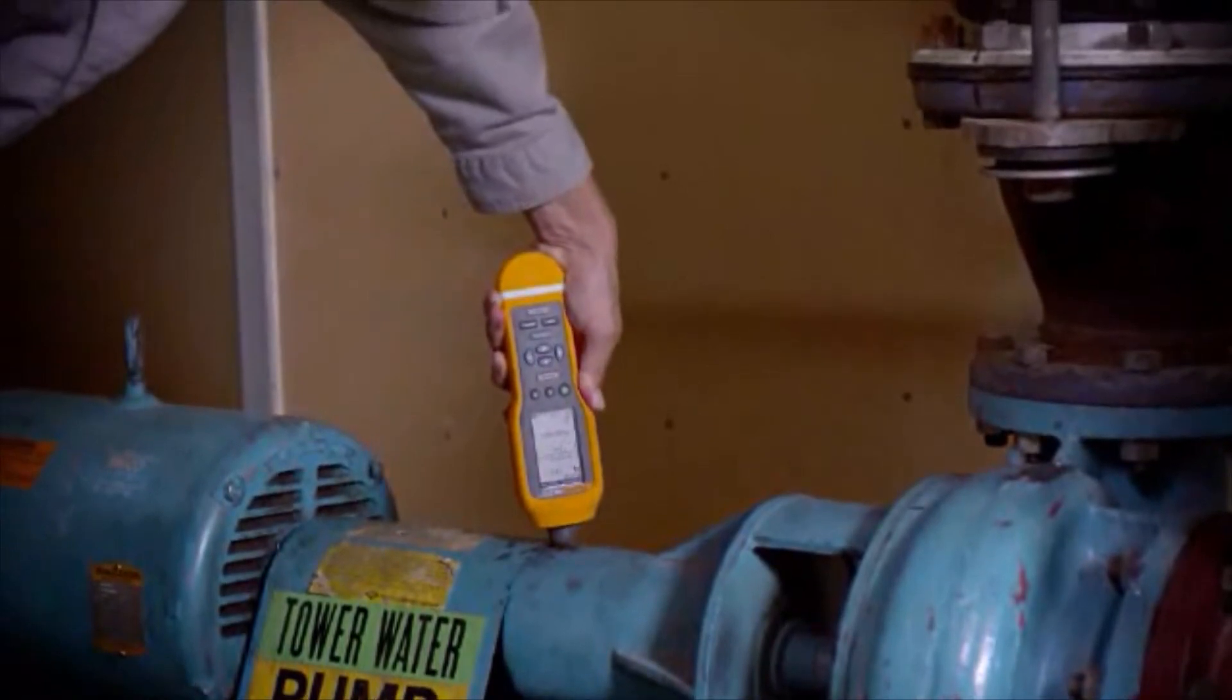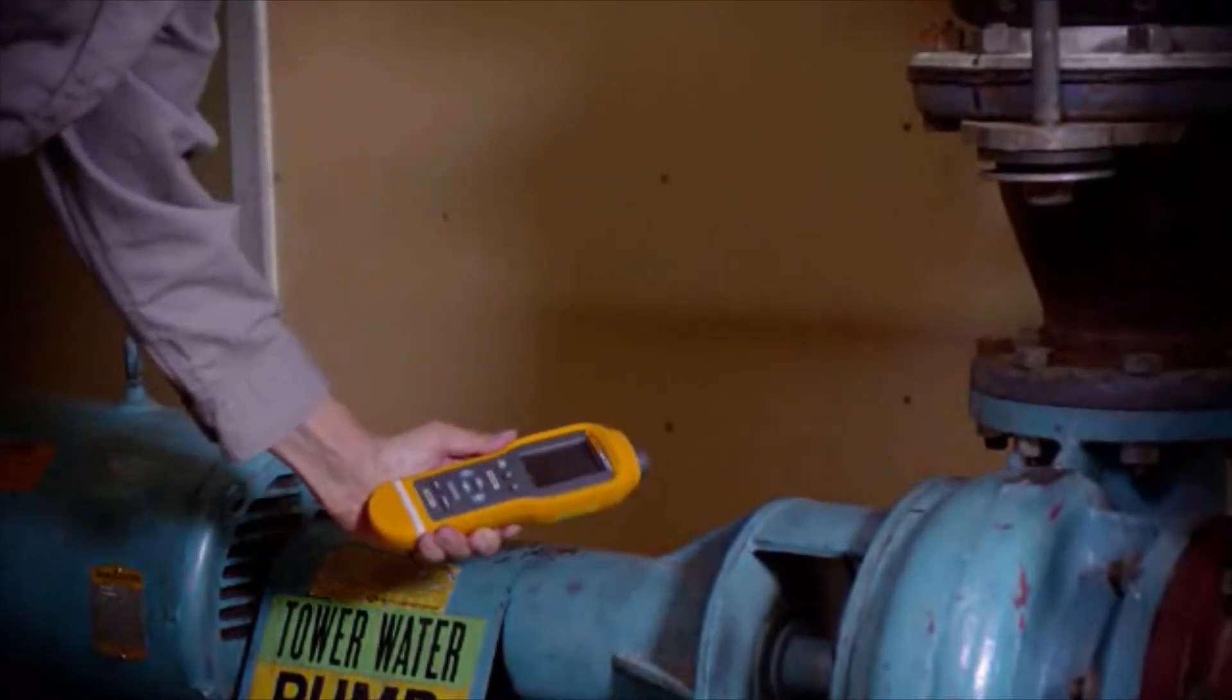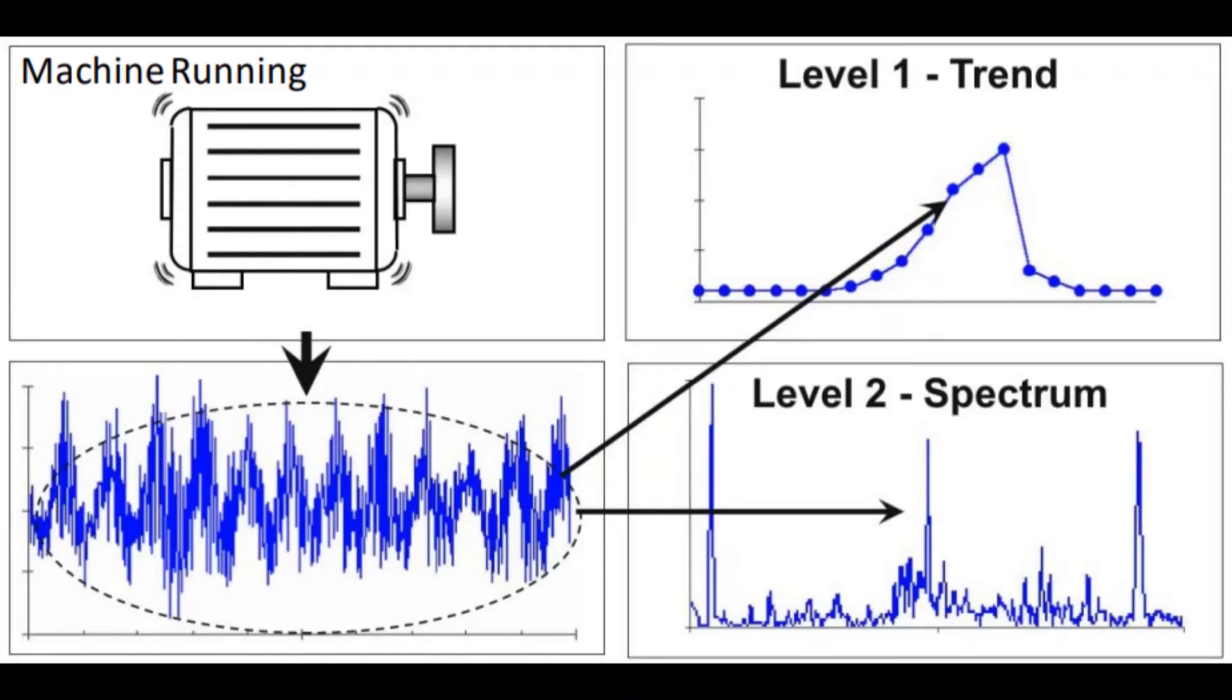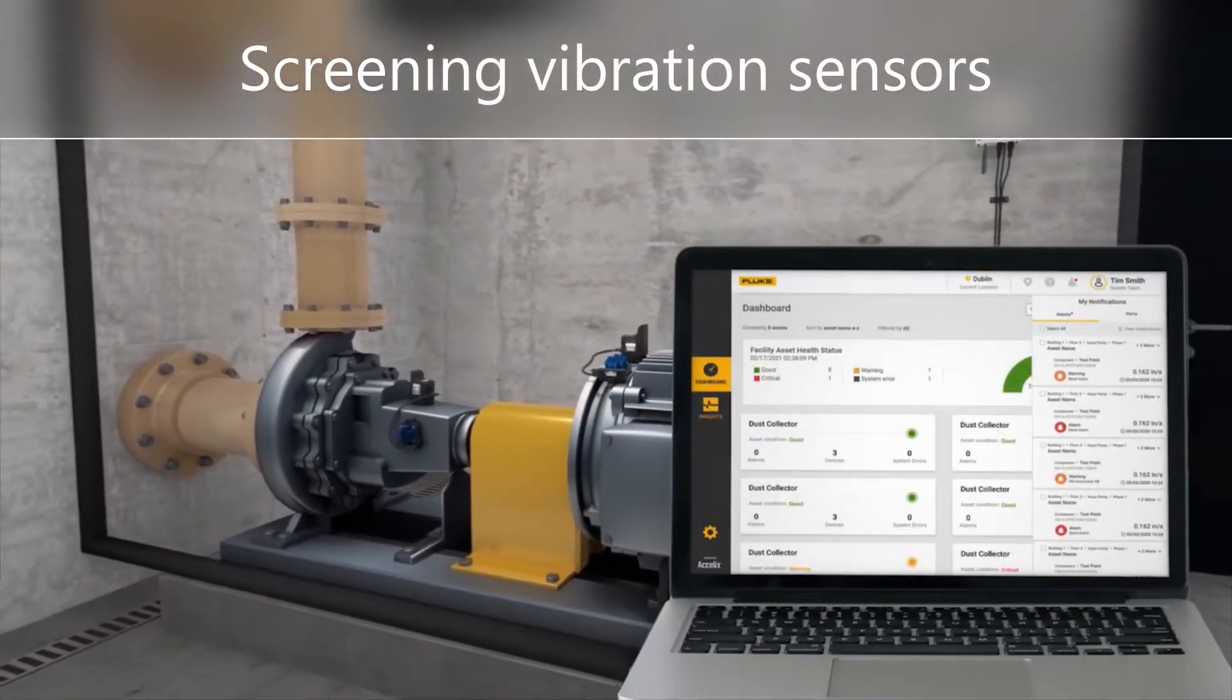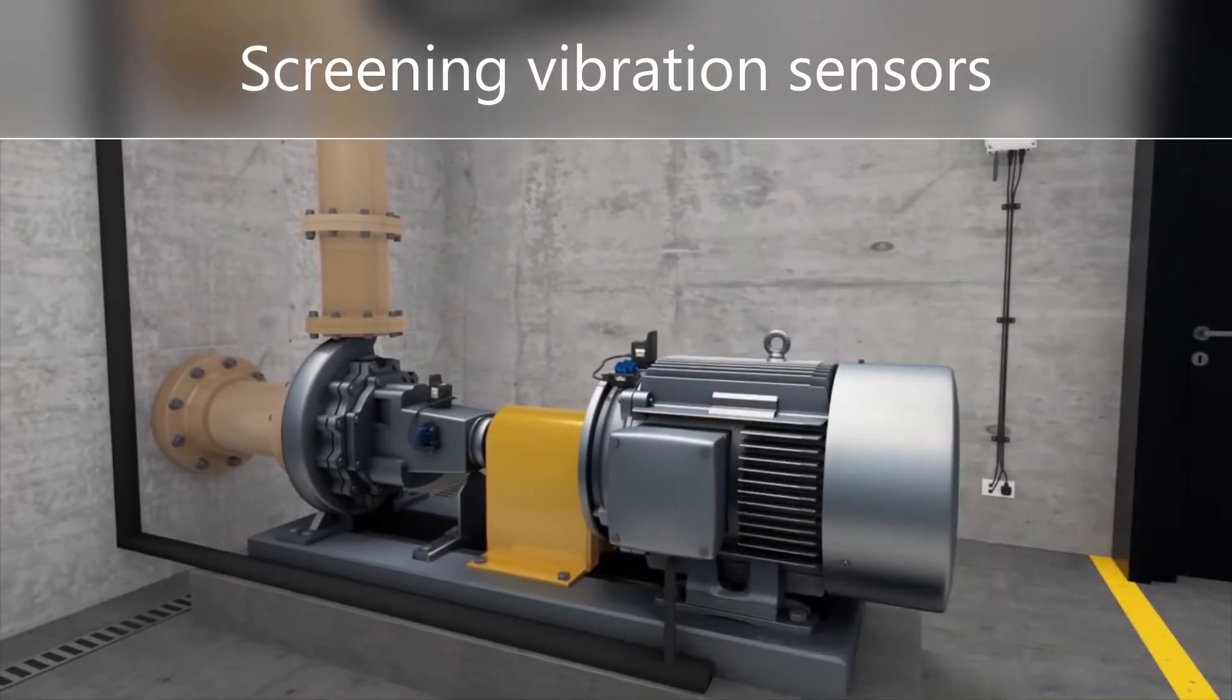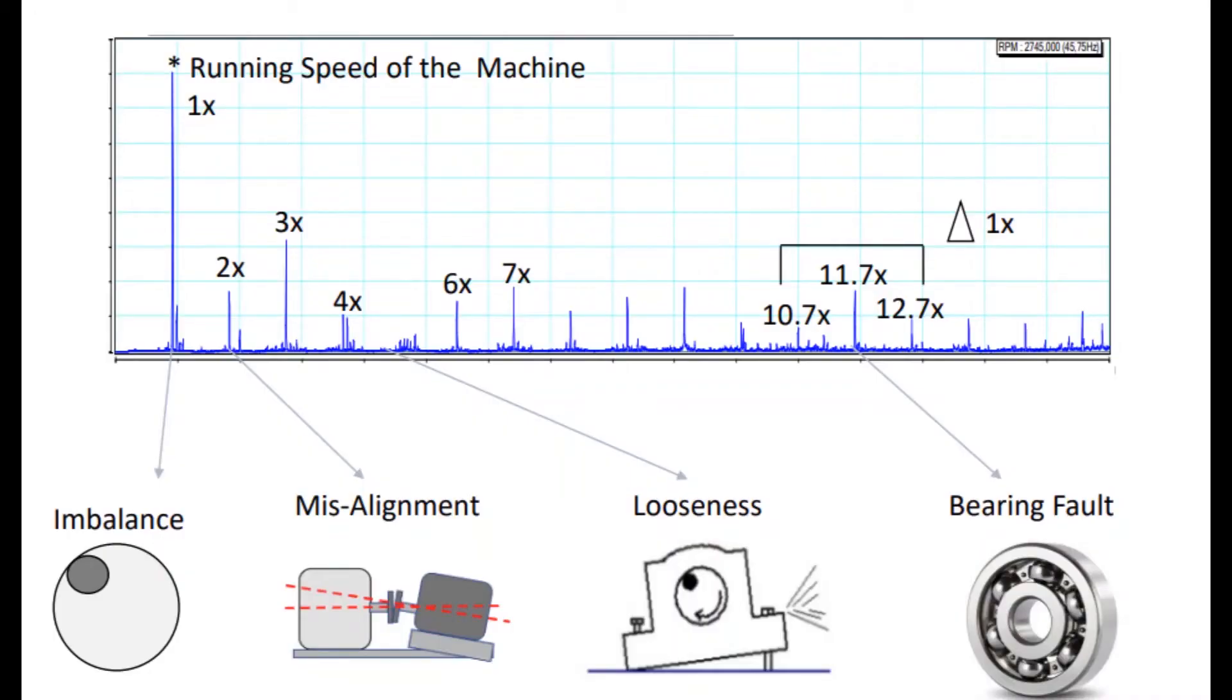Vibration screening is an effective way to screen a machine to determine if it is good enough to run or needs further testing. Trends of simple numbers and broadband alarms that look at all vibration sources quickly indicate potential problems. But just like blood pressure and pulse are easy to track, an increase could mean something is bad or nothing at all.